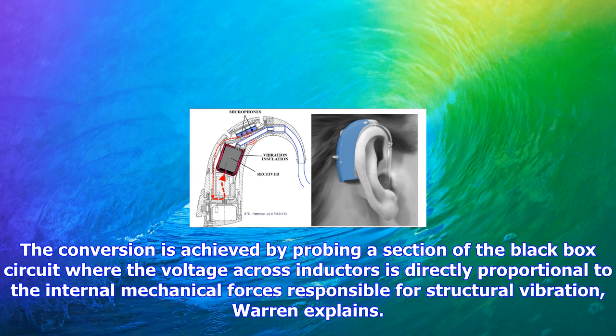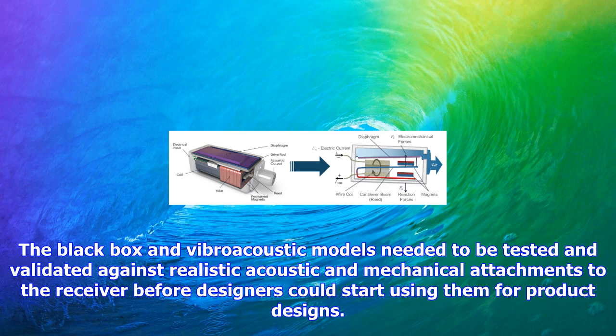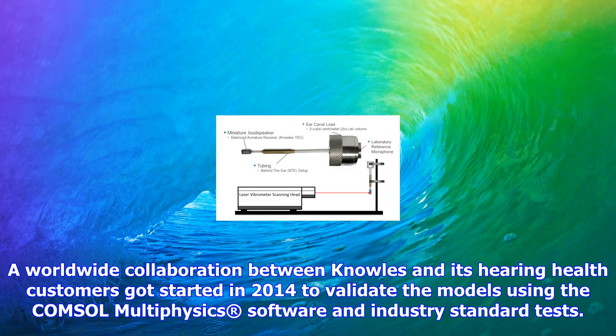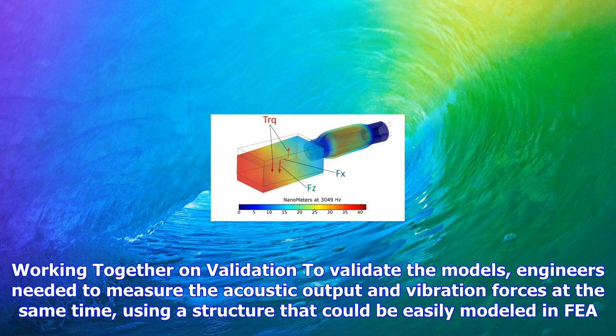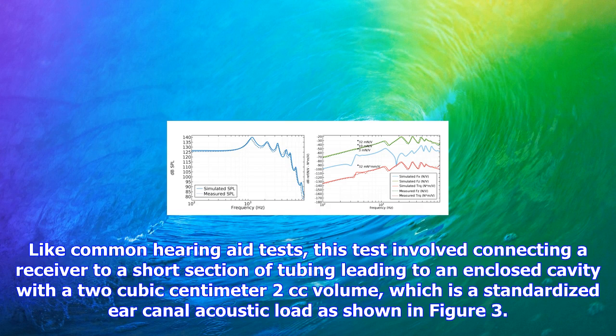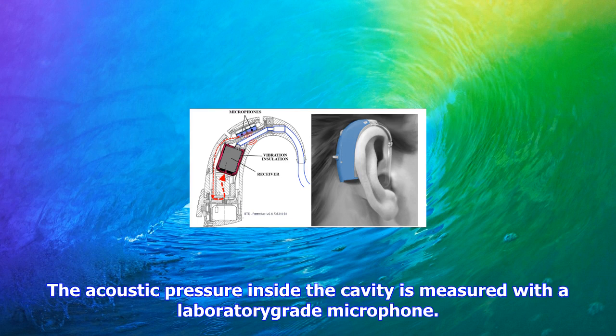The design uses a minimum amount of simple circuit elements to capture the essential electroacoustic transfer function between voltage and output sound pressure level for balanced armature receivers, while leaving out factors that are unimportant to feedback control. A key step to simplifying the model was when Warren and Veranda demonstrated that the simplified electroacoustic circuit could be converted into a powerful vibroacoustic model while adding very little complexity to the model. The conversion is achieved by probing a section of the black box circuit where the voltage across inductors is directly proportional to the internal mechanical forces responsible for structural vibration, Warren explains.